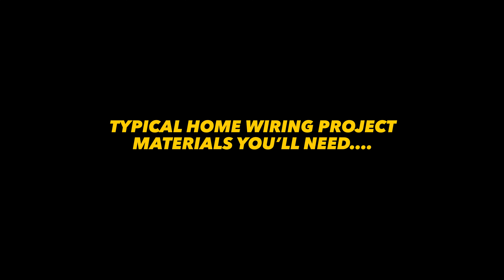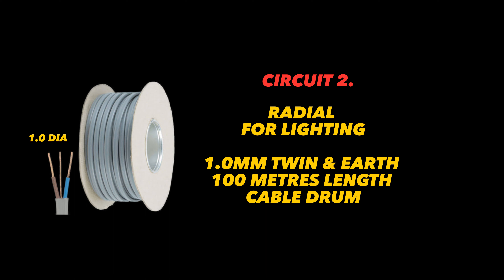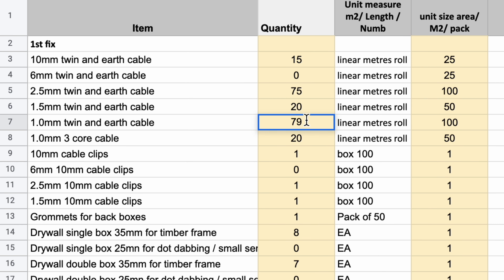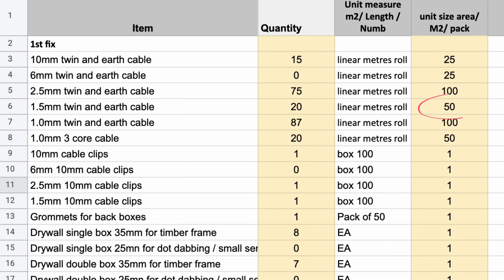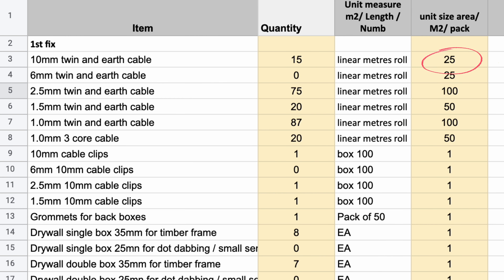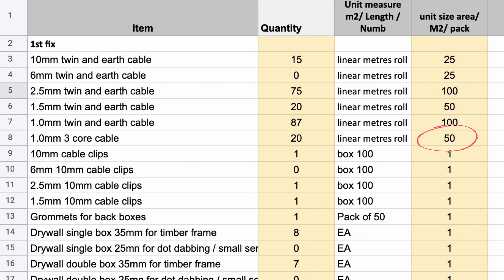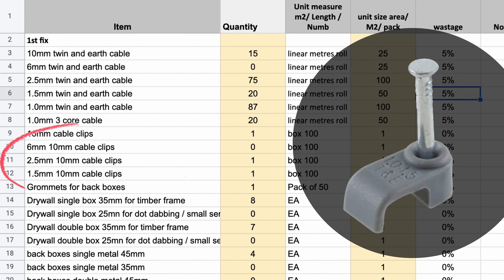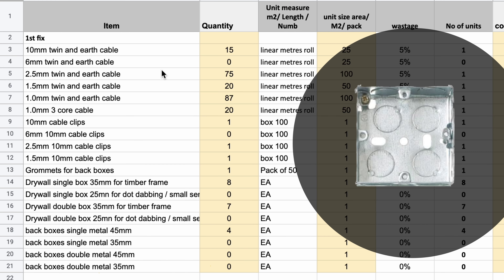First I need to buy my materials. I'll go for one 100m roll of 2.5mm twin and earth for my ring main, a 100m roll of 1mm twin and earth for my lighting circuit and switching, a 50m roll of 1.5mm twin and earth for my dedicated boiler supply radial, a 25m roll of 10mm twin and earth for my induction hob and cooker radial, and a 50m roll of 3-core twin and earth for my 2-way lighting and smoke detection, plus cable clips for each thickness.